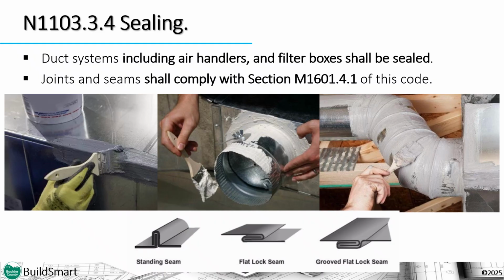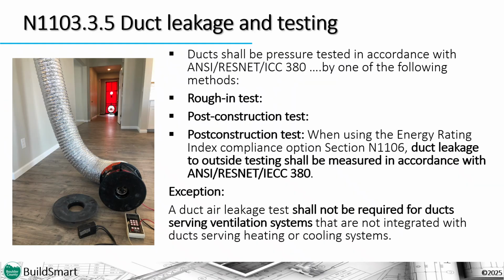And don't forget that air sealing the duct and the system as a whole while it's being built is the best practice. All HVAC duct systems are required to be tested regardless of where they are located. You may test at a rough stage of construction, which often makes the most sense, as if there is leakage, you can fix it prior to drywall. Or you're allowed to test at a final stage of construction, whichever works best for you.